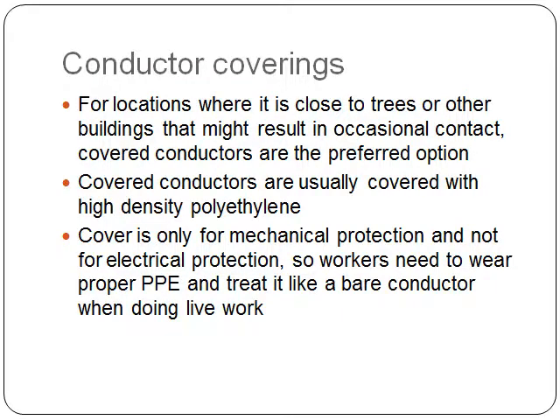For locations close to trees or other buildings that might result in occasional contact, covered conductors are the preferred option. Covered conductors are usually covered with high-density polyethylene. The cover is only for mechanical protection and not for electrical protection, so workers still need to wear proper PPE and treat it like a bare conductor when doing live work.